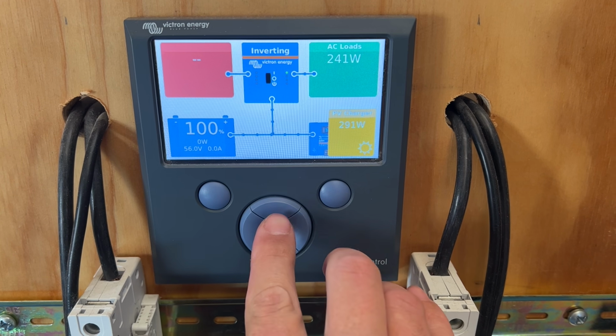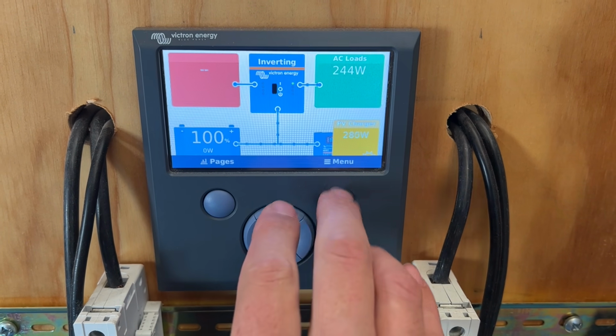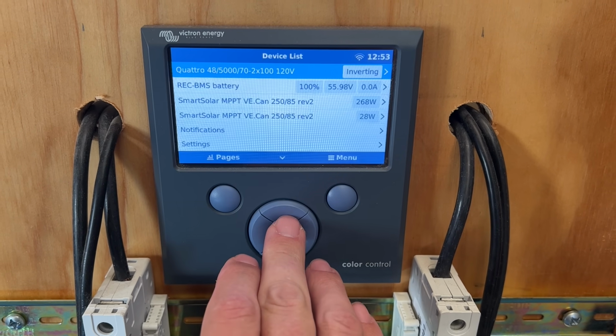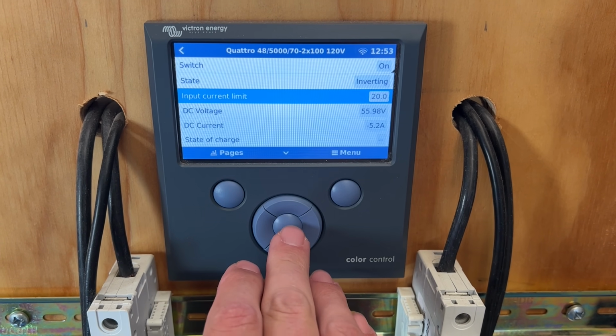I won't get into all the details here, you'll have to read the manual carefully, but once it's changed, you'll see the number for input current limit updated by going to Menu, Quattro Inverter on the Color Control GX. Supposedly you can also get in and change this with a special cable and software on your computer, but we haven't tried that yet.